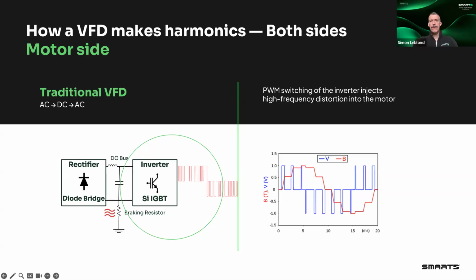What that does is that the motor sees these rapid voltage transitions, and this causes dV/dt stresses. That's when you get into the reflected wave phenomenon for long cable runs. You also get common mode currents that flow through the bearing. So this is why you will get specially rated cables for those long runs. You'll put in extra filters. You'll get inverter duty motors to handle that extra voltage stress. You get shaft grounding rings and insulated bearings for the common mode currents.